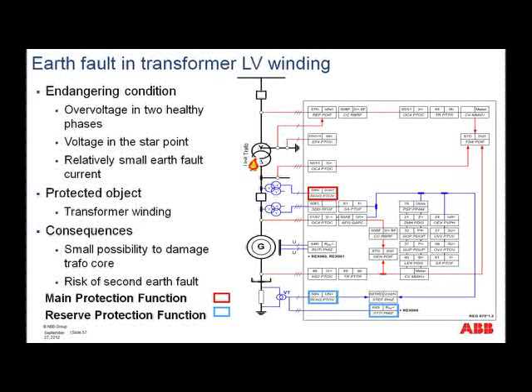If we have a fault in the transformer LV winding, now this is the delta winding, and here really the main protection for this would be a residual overvoltage function, but it would also be able to be seen by the overvoltage earth fault protection on the star point. And if you were using the injection principle, this injection would also be able to see this.